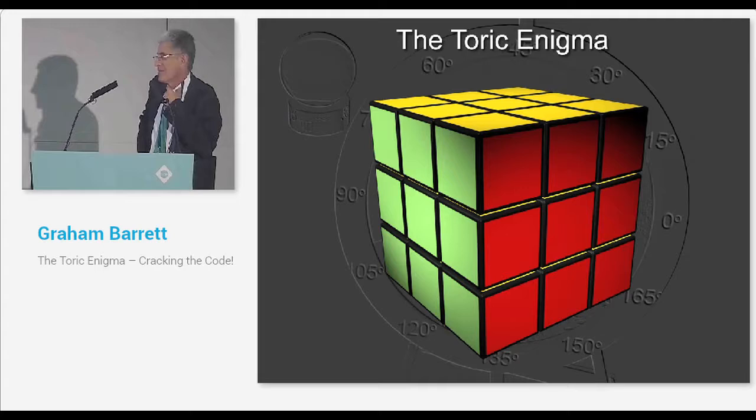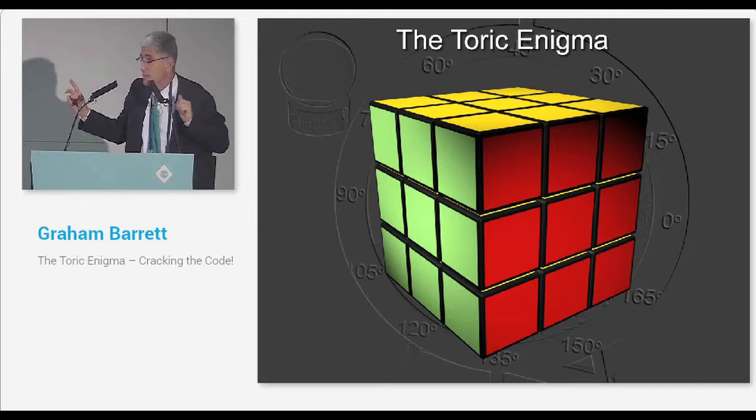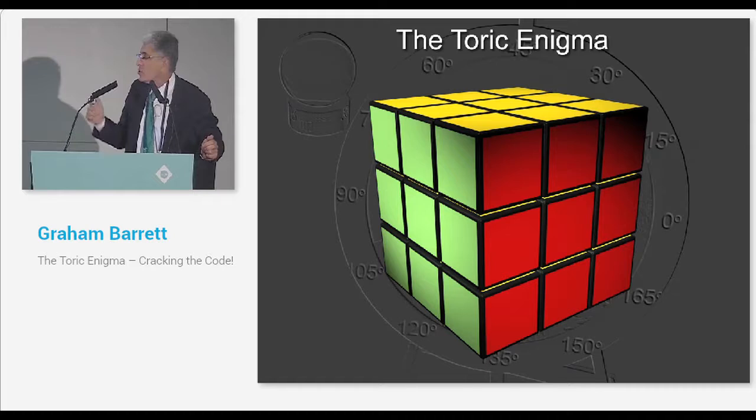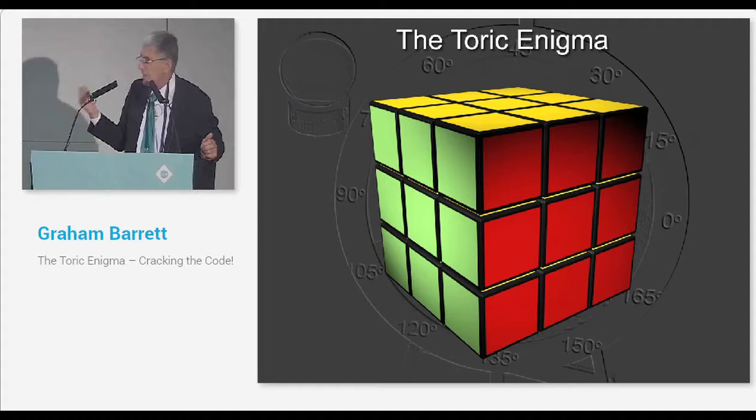Just a quick question. What is your primary instrument for the keratometry? For marking? For actual marking, he's talking about the steep meridian pre-op, to find it out. Look, I do three things. I use a LENSTAR or Biometer or IOLMaster. I use a Javal, a manual keratometer with a good observer, and topography. I use Pentacam. I'm looking at those three and confirming that my Biometer's giving me the right axis. Because unless you do, maybe you can get away with two, or maybe LENSTAR topography may be enough. But at the moment, I'm using three to confirm I've got the right axis. The IOLMaster in particular will sometimes give you spurious readings. Not often, but occasionally.